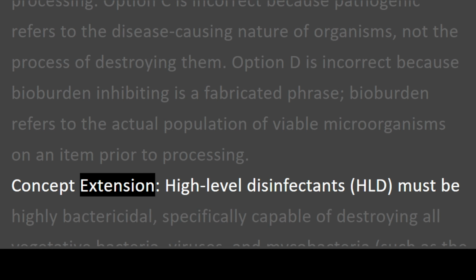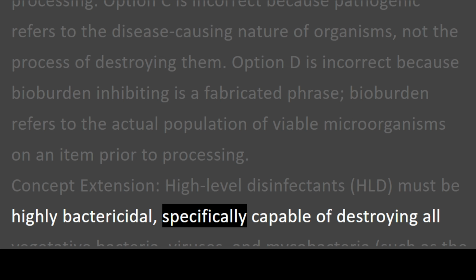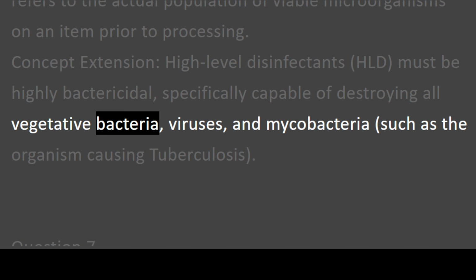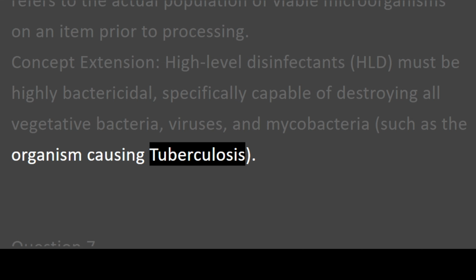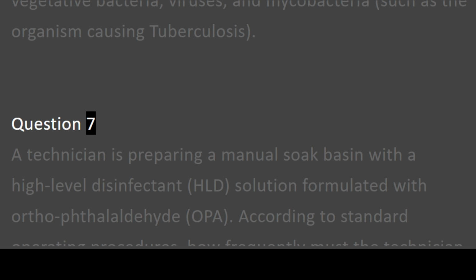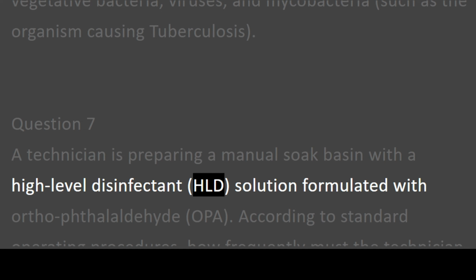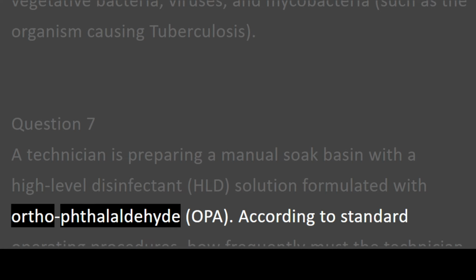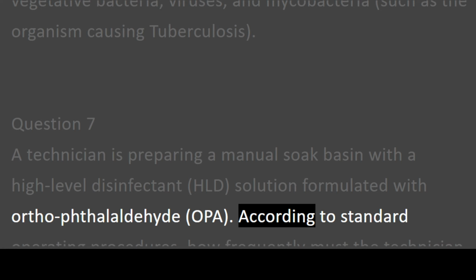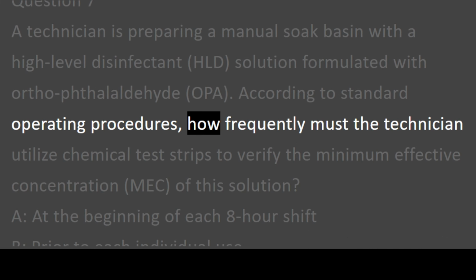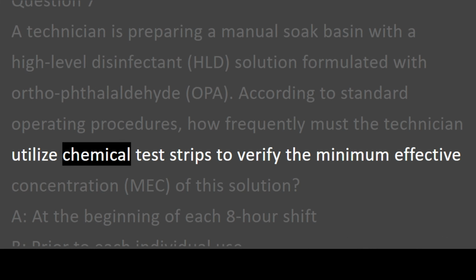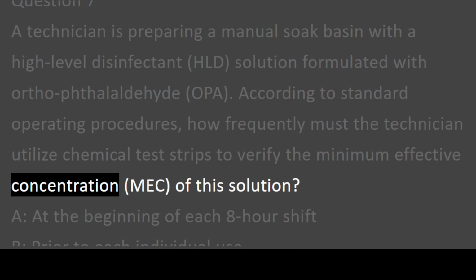Concept extension. High-level disinfectants, HLD, must be highly bactericidal, specifically capable of destroying all vegetative bacteria, viruses, and mycobacteria, such as the organism causing tuberculosis. Question 7. A technician is preparing a manual soak basin with a high-level disinfectant, HLD, solution formulated with orthophthalaldehyde, OPA. According to standard operating procedures, how frequently must the technician utilize chemical test strips to verify the minimum effective concentration, MEC, of this solution?